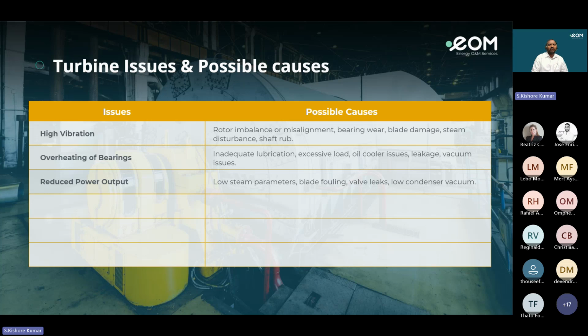Reduced power output is caused by low steam parameters, blade fouling, valve leaks, and low condenser vacuum. So we can see there are a lot of leaks, and running the turbine at low vacuum is the major cause of reduced power output. Coming to the vacuum, a lot of the time people don't perform the helium gas test or foam tests to find any leakages or gaps. If we do that, we can avoid the vacuum losses, and so avoid the reduction in power output in the turbines.